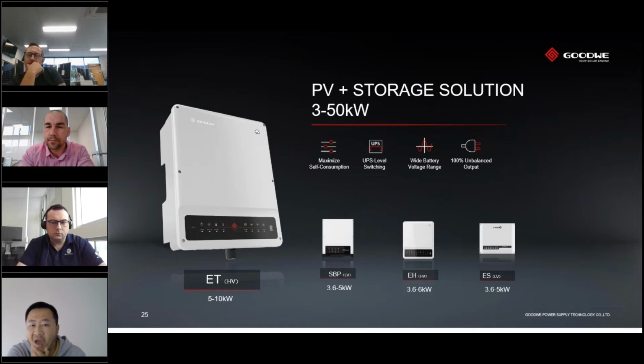And in terms of our storage inverters, we really break it up into 4 different categories. The first one is our 3-phase hybrids. This is called the ET series. We have that now in a 5, a 6, an 8, and a 10. Previously, we only had it in a 5 and a 10, but we've also now released the 6 and the 8 kilowatt in this series as well. This is a high voltage hybrid solution, so therefore can only be paired with compatible batteries. And we also have a compatibility statement if you need that as well.